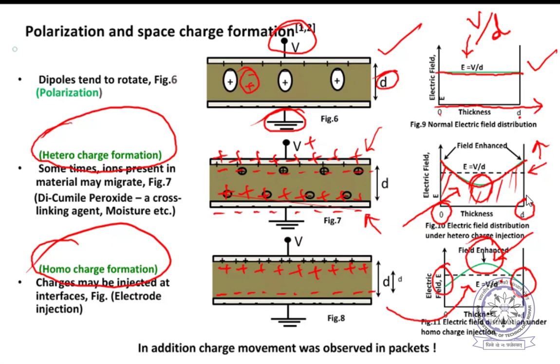See, one thing we have to observe is that failure at one place is equivalent to failure overall, because it is like a weak link mechanism. Weak link mechanism means if you have a chain like this, if one of the links fails, it is failure only, even if the rest of the insulation does not fail. So overstressing at a particular location is equivalent to stressing and failing the entire insulation, because if one spot burns, that is the meaning. So we are concerned with this charge formation, which is actually happening in the cross-linked polyethylene insulation.